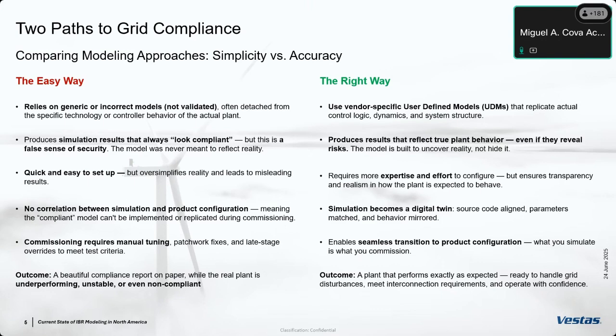It's very complicated, time-consuming, and expensive to find a grid compliance issue with a plant that's already operating. When that plant is operating and curtailed by the ISO, this results in a loss of production that will be claimed against the OEM or the generator owner because the plant was not performing as expected. So it's better to capture the wrong, incorrect, or undesired behavior early enough and not when the plant is in operation.